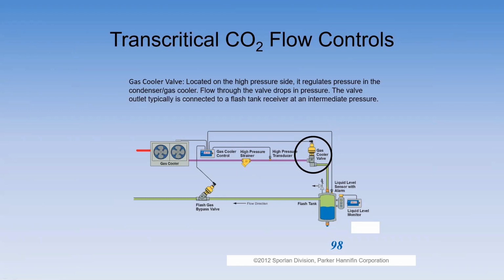It's not going to be as deep as regular systems, like 404A, where you might have 7, 8, 10, 12 degrees of subcooling. You're doing well if you get 2, 3, or 4 degrees of subcooling with CO2, but generally that's good.